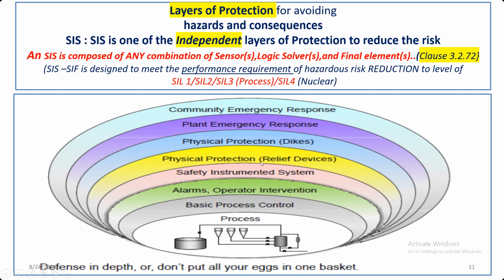Then the fourth layer is SIS, which we are all talking about. SIS is a very flexible layer. You can have this layer designed for SIL 1 performance to SIL 3 performance for the process industry. So this takes care of whatever is not addressed. If the process fails, BPCS takes care of it. How many of you believe that your process control system or controller can never fail? If you have that thinking, it's wrong thinking. Process control can fail. In the second layer, operator intervention, the operator can also fail because the operator is a human. And then SIS can also fail.